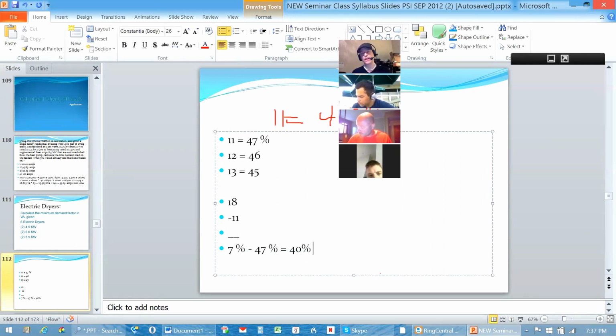Or 5,000 watts if they happen to be 4,500, or if they don't give you a value at all, if they just said 18 dryers, what would the calculated value be? Then it's just going to be 5,000 watts, because that's my minimum I have to have under the article. And then my derating would happen just like that. So I would end up ultimately taking 5,000 watts and multiply that times the value of 18 units, which gives me my total connected load of all of them at 100%. So 5,000 times 18 units would give me 90,000 VA or 90,000 watts. And I would then multiply that against my new calculated derating value of 40%.